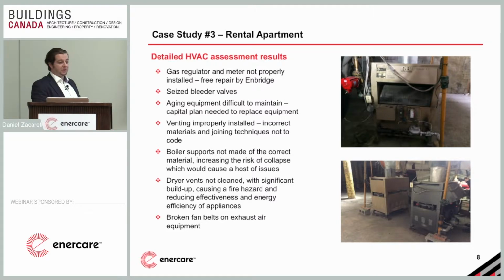Boiler supports, for example, something that's quickly overlooked. We had a few boilers here. If you look in the bottom right-hand picture, one side of it is held up by a brick, another side is held up by a piece of wood, another side by some shims. As the wood degrades, the boiler starts to shift. As the boiler shifts, the connections break. As the connections break, you fill your boiler room with hot water. We recently had a customer whose boiler room filled with 5 feet of water before they realized their boiler room was full of water, and then they had to replace everything - 3-year-old, almost brand new boilers, their pumps, the electrical in the room.